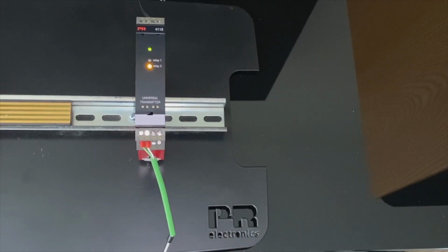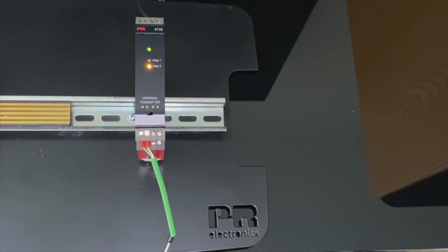So why do we call the 4116 a universal transmitter? Well, first of all, the 4116 can be powered with either AC or DC voltage. Doesn't matter. It is a signal conditioner. It provides signal conditioning, as you'll see. It is an isolator with 2.3 kilovolts of isolation. It also will perform scaling. And probably the most important reason is that it has multiple inputs that you can add to the unit, and it will provide 2 relays and an output signal. And we'll get into the particulars of those things.